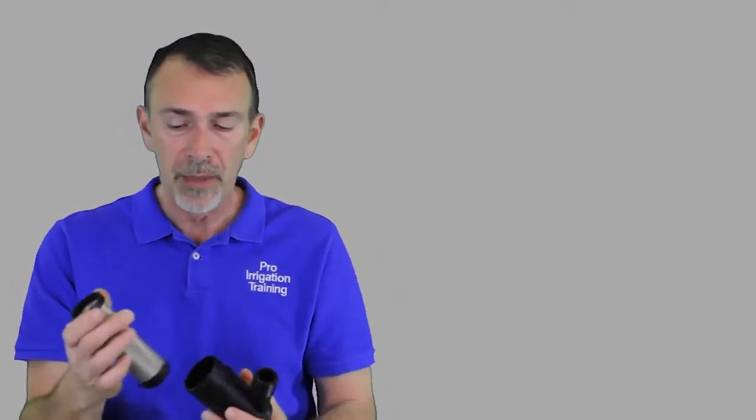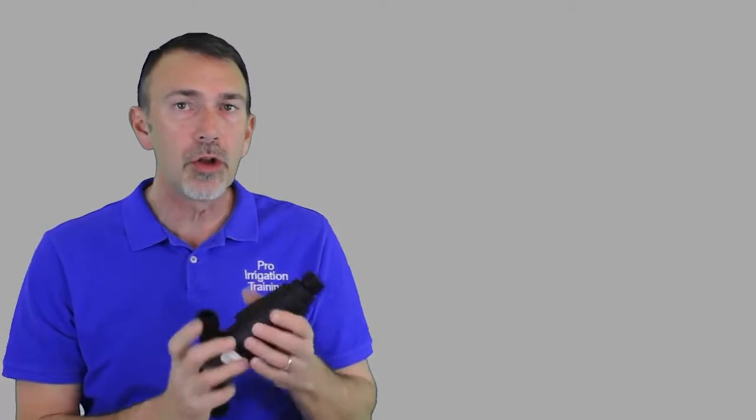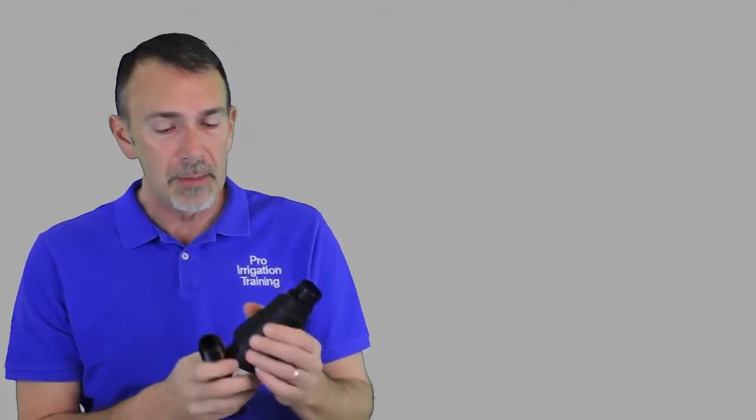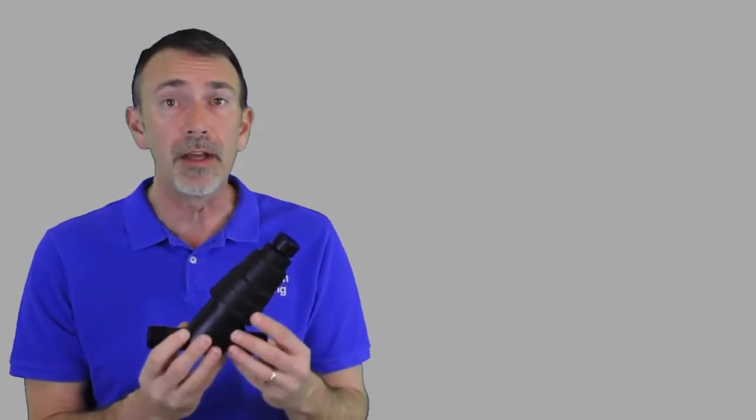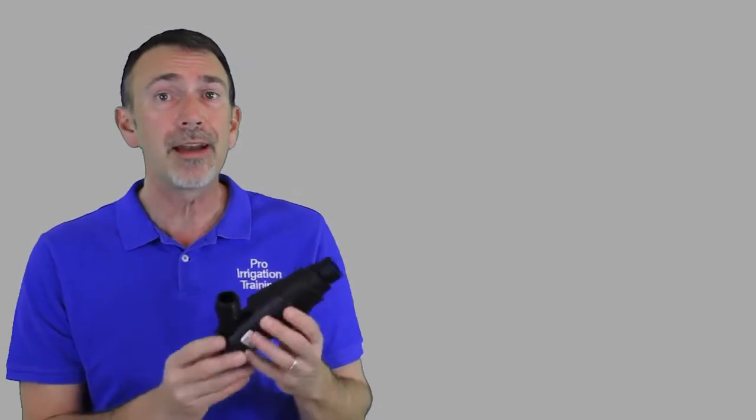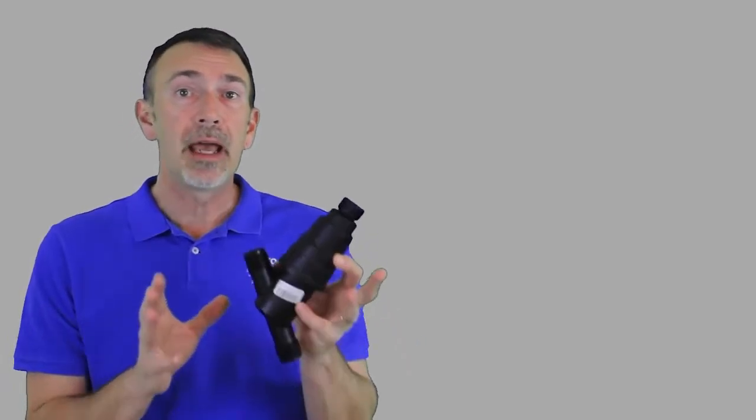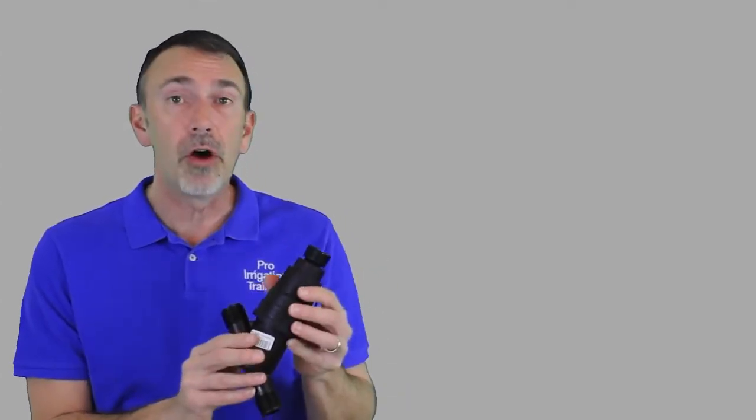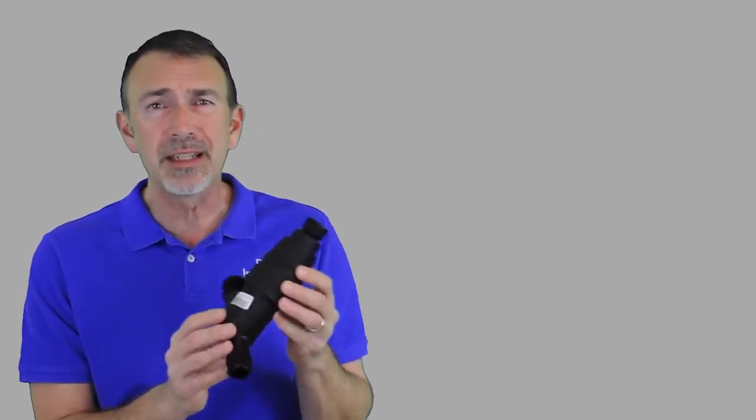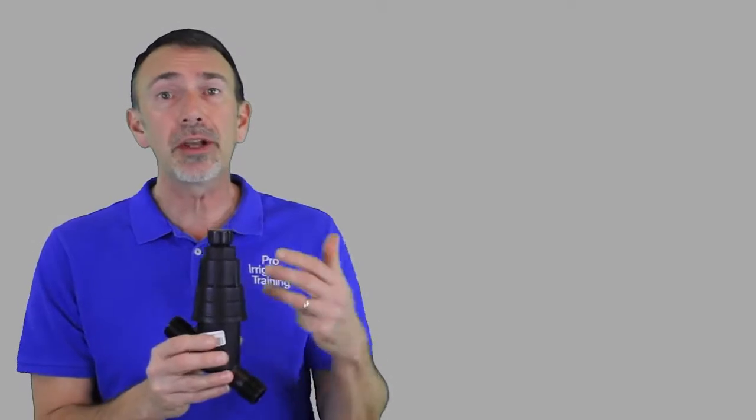And then as the water is on the outside of the cup inside this basket, it flows out the other end. Of course it's under pressure. And what's going to happen here, sometimes you need to pay attention to the amount of pressure loss that's going to happen. So let me put this into perspective. Some filters have greater amounts of pressure loss in it because of either the size of the screen or the configuration of the body of it. But on this particular one, if you've got 10 gallons per minute flowing through it, you're going to have PSI loss of about three and a half PSI. To put this into perspective, a typical one inch elbow has about three PSI loss on average. But if you get up to 15 gallons per minute through this, then you're going to have six and a half PSI loss.